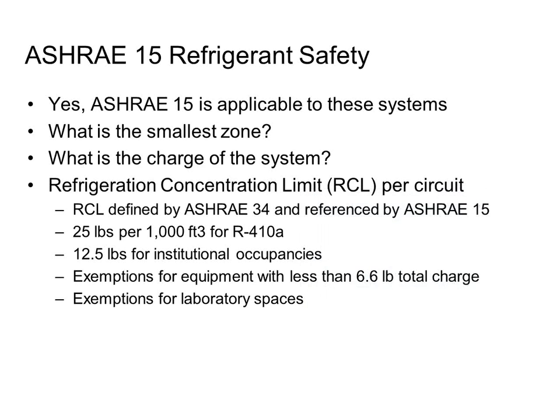If I've got refrigerant pipe in the corridor, I've got to make sure that I'm under, in this case 5,000 cubic feet, so I have to be under 125 pounds of total refrigerant charge, which I should be able to do fairly easily. So unless you have a very small corridor, this is probably not going to be an issue at all. But it is one of the spaces you would have to look at if your refrigerant lines do run down the corridor of the building.